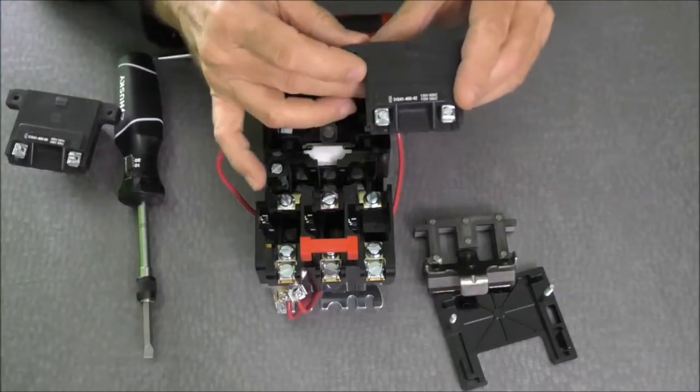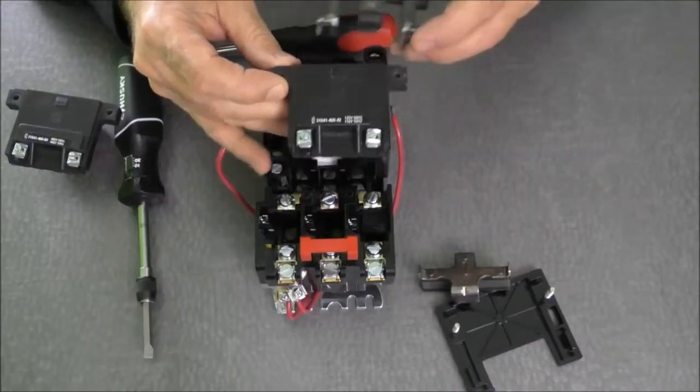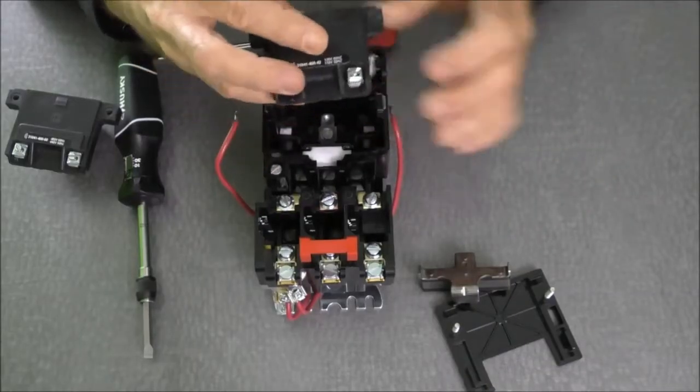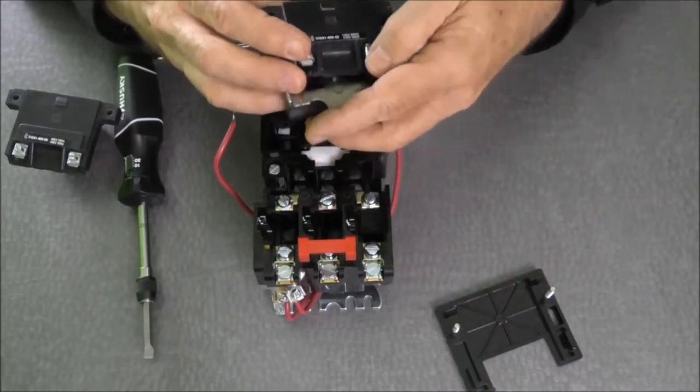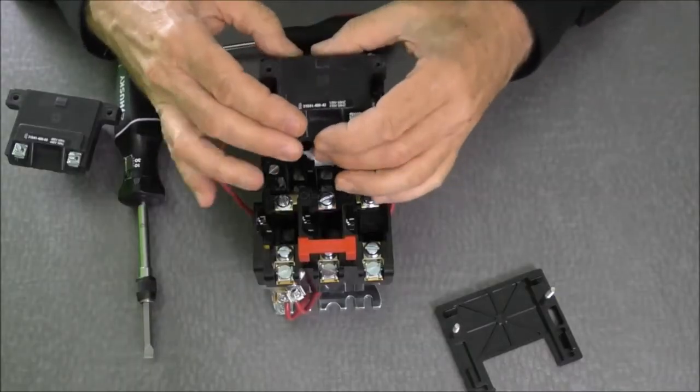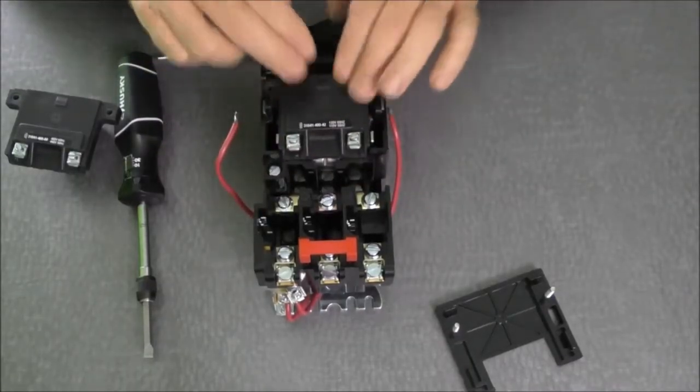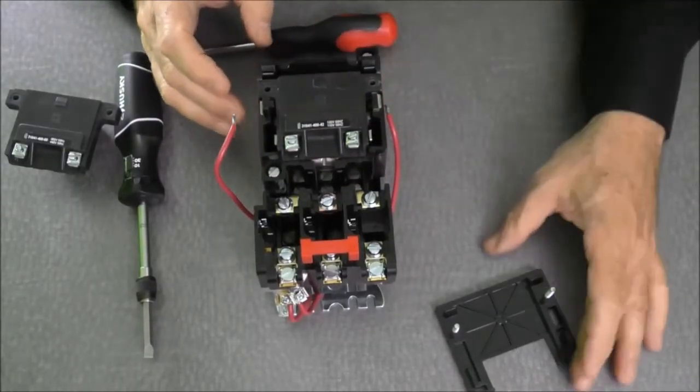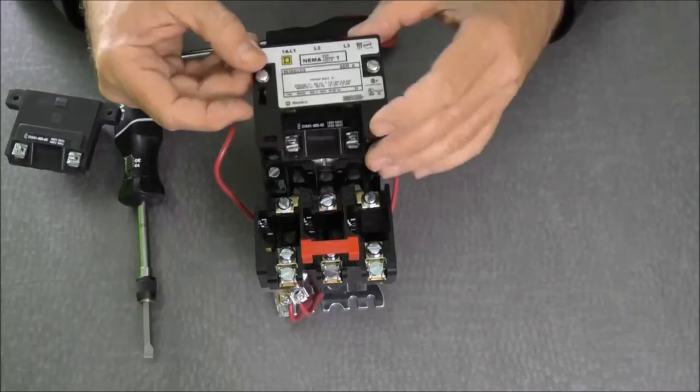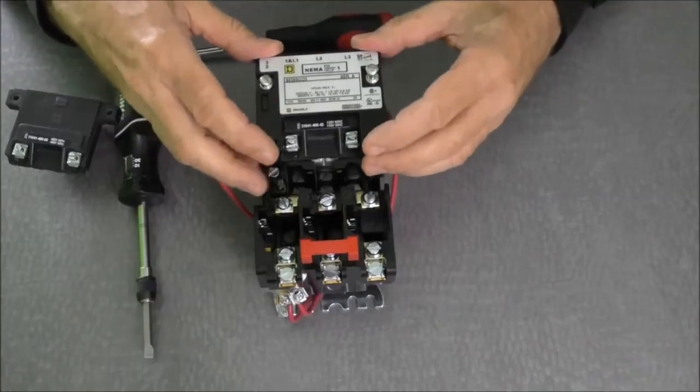I will then pick up my 120 volt coil, put in my magnet, put in my armature, slide it back into the starter itself. I can now take my cover plate and replace it on the contactor.